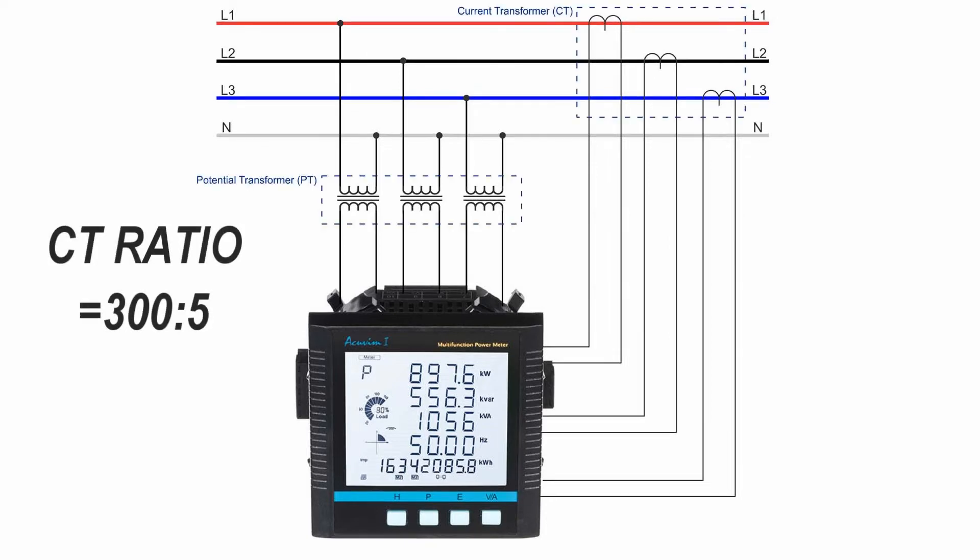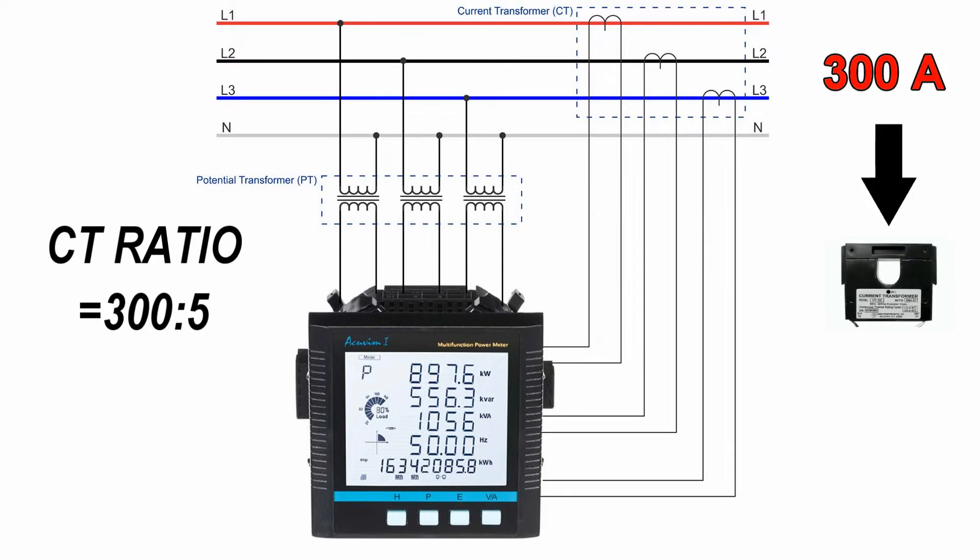For example, if a CT has a ratio of 300 to 5, it means that when the CT sees 300 amps of current from the grid, it will output 5 amps to the meter and PTs work the same way.